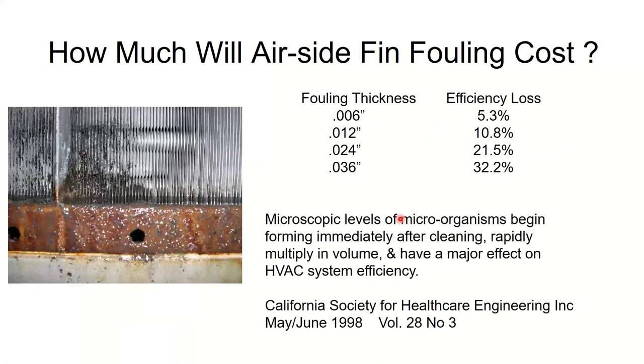If you keep the coil clean, it does both a better job of heat transfer. BTUs can move through the metal better than they can move through the metal plus the dirt or the metal plus the growth of whatever's on there. And they also do better on the airflow side. The less crap built up on the coil and less stuff growing on the coil, the more airflow will be able to flow through it. So there are a lot of benefits to putting a UV light on the coil, but keeping air in a room clean is not one of those benefits. Now, you can say it keeps the air in the room clean because stuff's not flaking off the coil and ending up in the airflow because the stuff is dead, but it's not going to kill germs that are already in the room. So it's good at cleaning the coil, not good at cleaning air in a room.